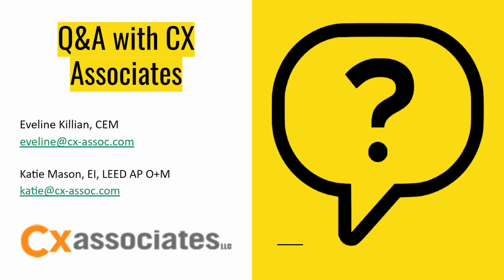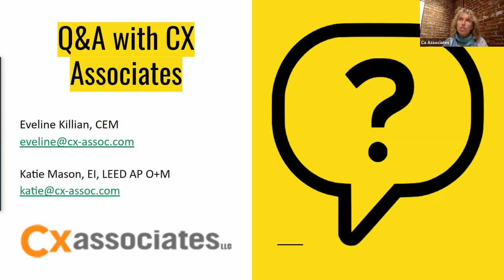Okay, and our second question, what does an airflow test or an assessment look like, and will it affect business hours? That's also a good question. So what we do is we bring in, and I'm sorry, I don't have an example of it with me, an airflow hood, which is probably about 1.5 feet long, and we put that to any diffuser that you have in your spaces to analyze how much airflow is already coming into the space. That's really the only work that we do in the occupied space. If we're looking at a ventilation unit, we will go to that, which very well could be, and a lot of times is, on the roof or in a closet.